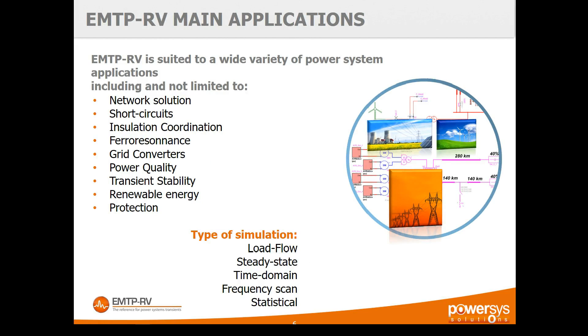Here are the main types of application of EMTP. Starting with the network solution — solving a load flow. EMTP is a time domain software, but it also has very powerful load flow capabilities: single-phase, multi-phase, balanced, or unbalanced. Initially, we used load flow to initialize the network. When you have synchronous generators or loads, you cannot start a time domain simulation without initializing them — you need to know the angle of each machine so the power flow makes sense.